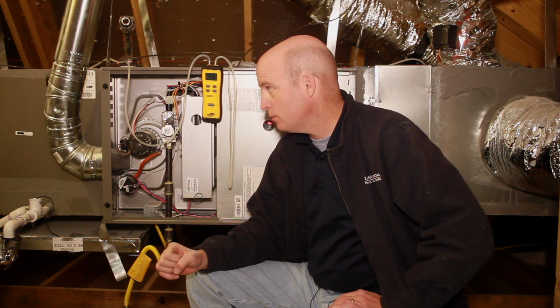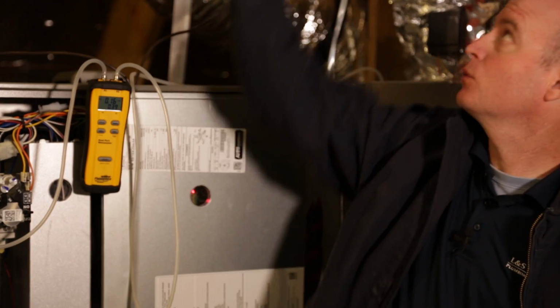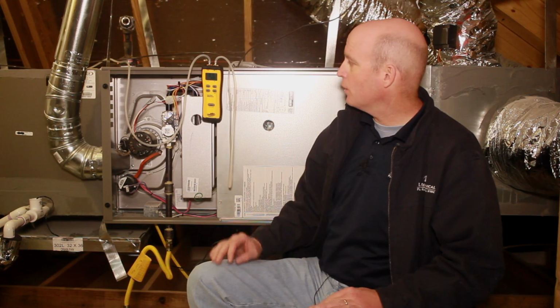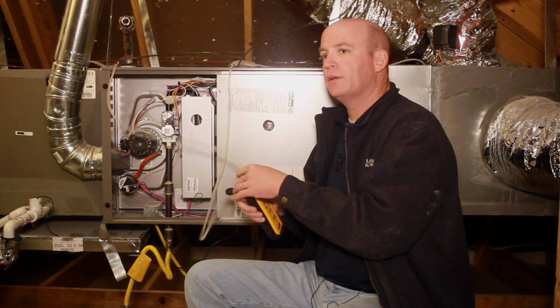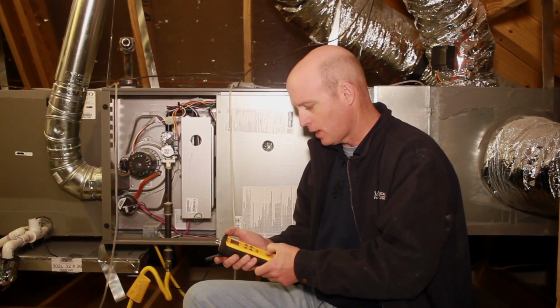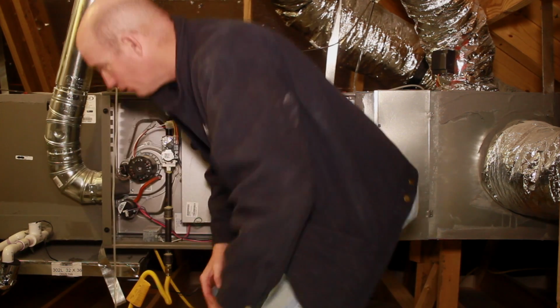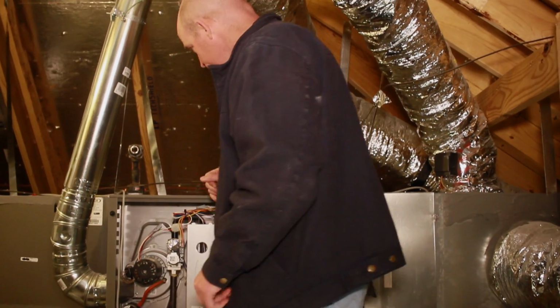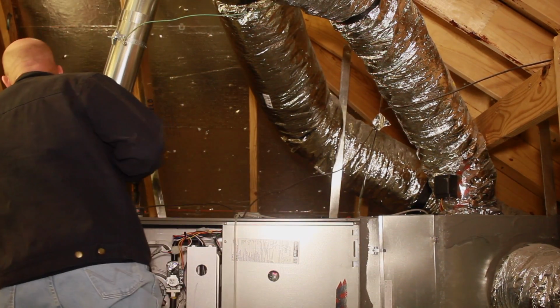In an extreme circumstance, we could have an issue in the evaporator coil with drywall dust. But some of the times you're lucky enough with the ductwork like this, you could find it kinked in the attic. Now that we're all done, we can go ahead and turn off our meter and disconnect, get all of our probes put up in the toolbox. We're going to have to address the holes, and we'll show you. There's a nifty way to do that.